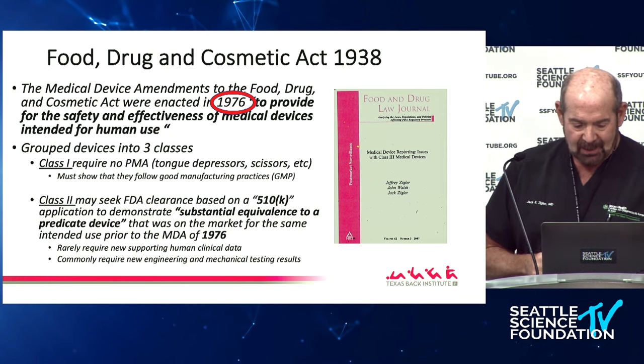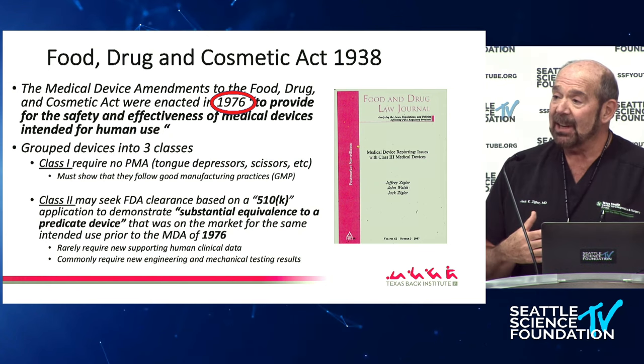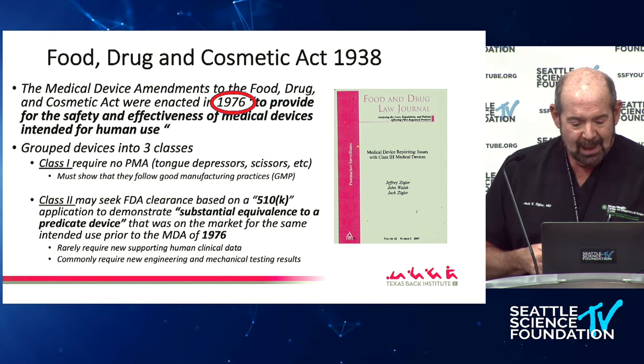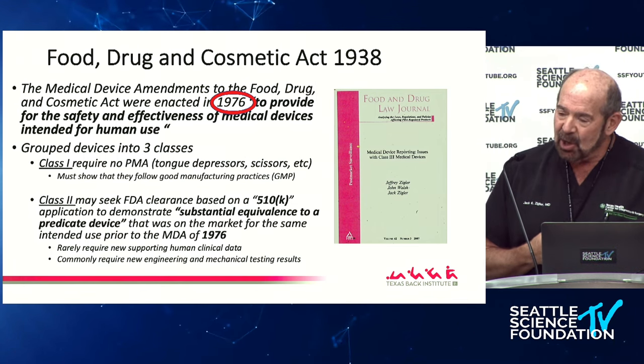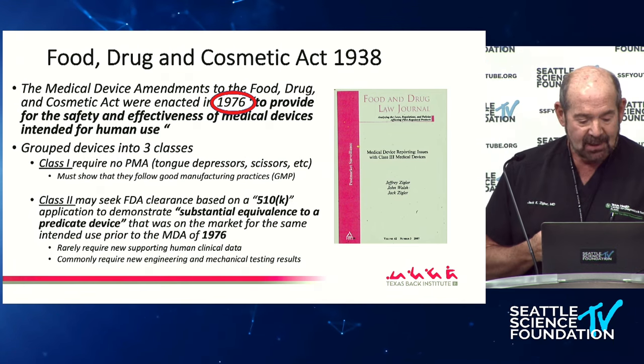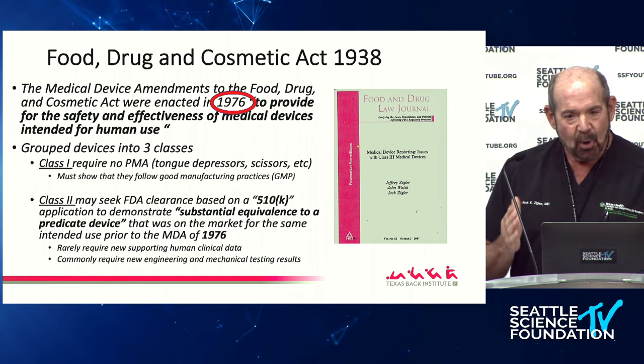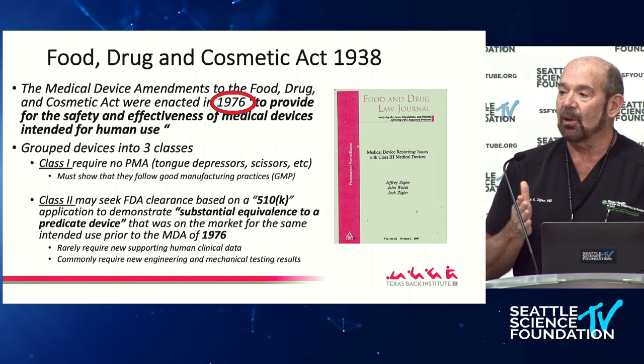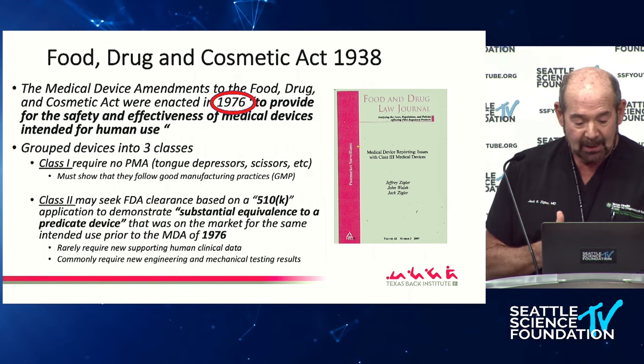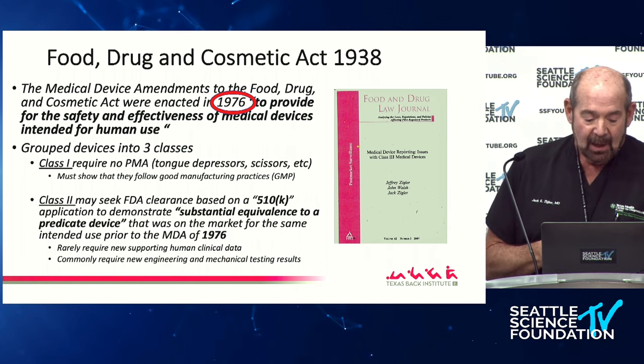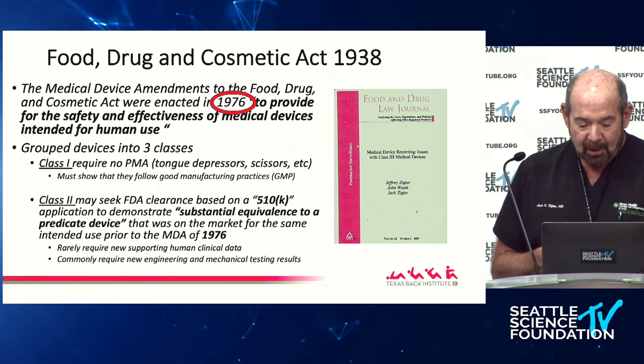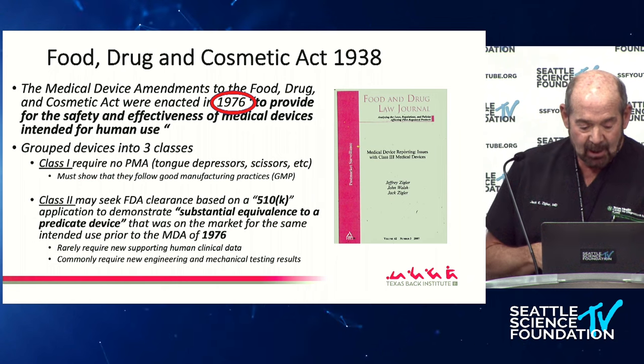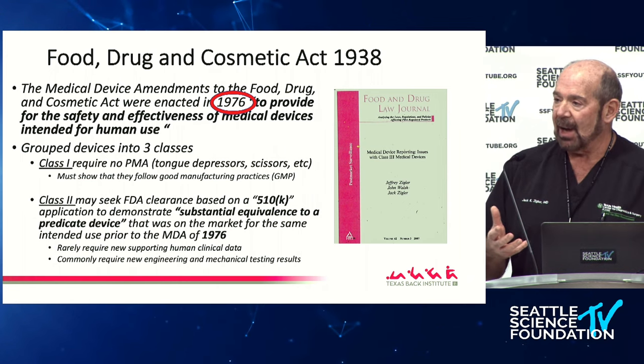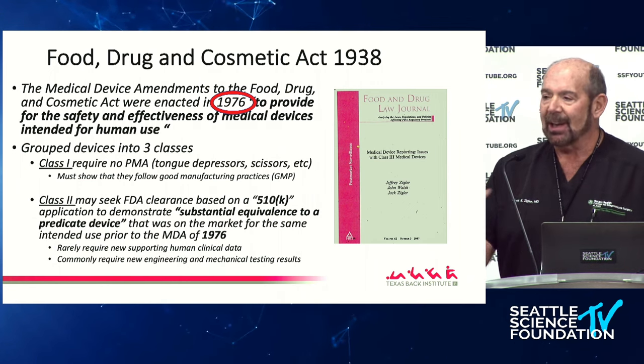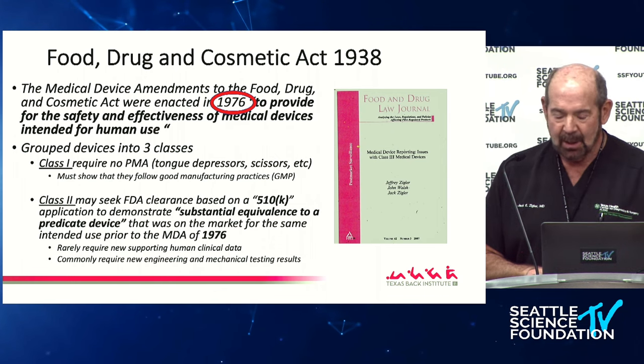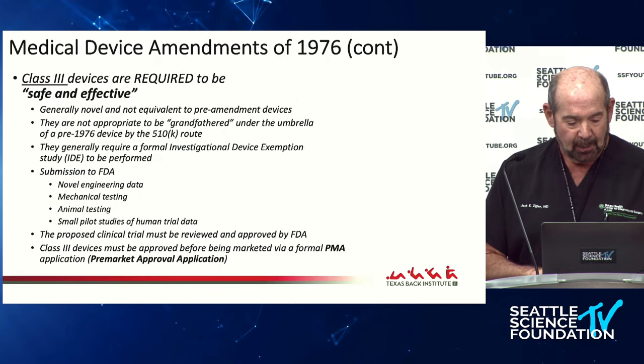Class two devices may seek FDA clearance if they can show that they were substantially equivalent to devices that were on the market prior to 1976, when the medical device amendment was passed into law. So those rarely require new supporting human clinical data, although they may need to provide appropriate engineering and, of course, the same manufacturing seal of approval.